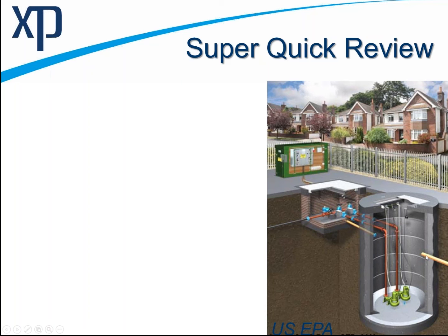To the right comes in gravity flow, theoretically. It doesn't have to be gravity flow, but water comes in, drops down, fills up this wet well, and then you see a level indicator to tell the pumps when to turn on. It looks like there's one right here, the low level, and then maybe the high level or alarm. These pumps have no suction line. They suck directly into this centrifugal pump and then discharge out and up.